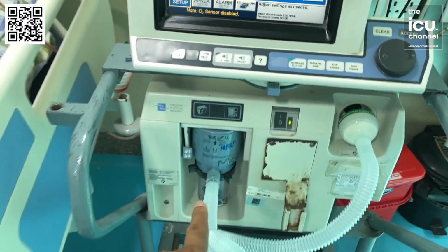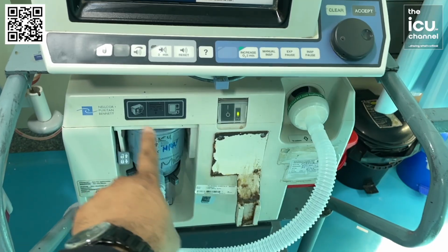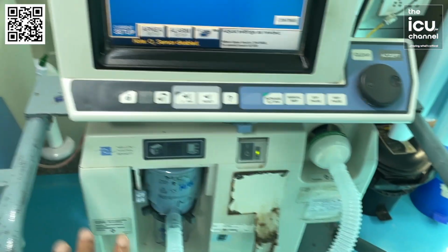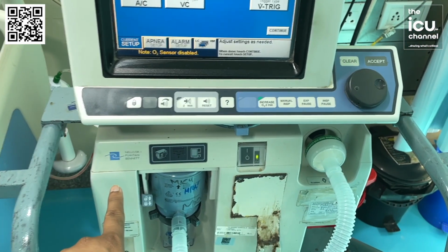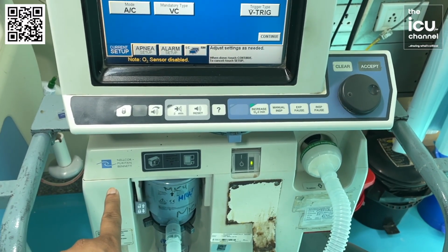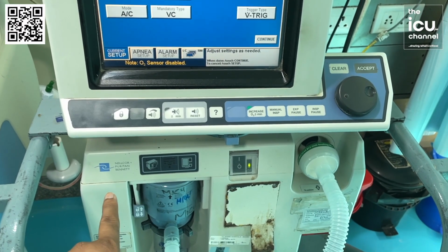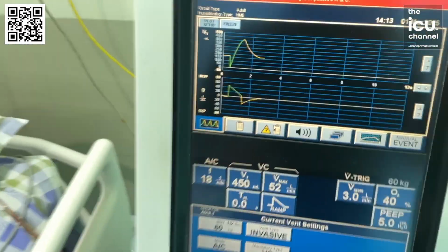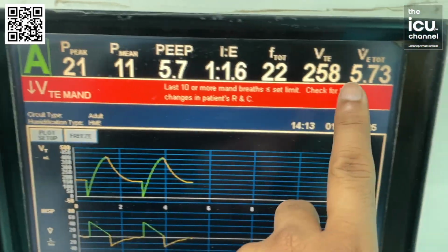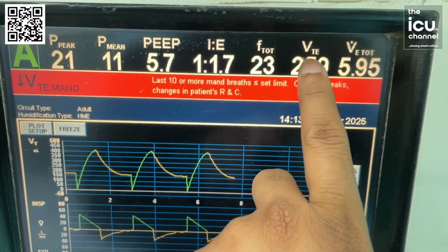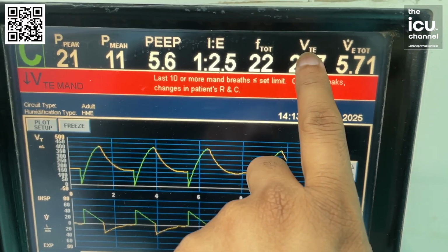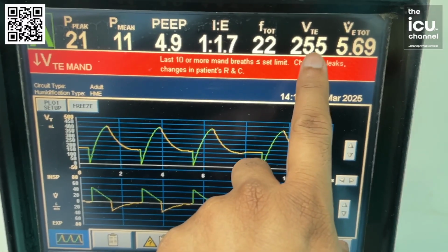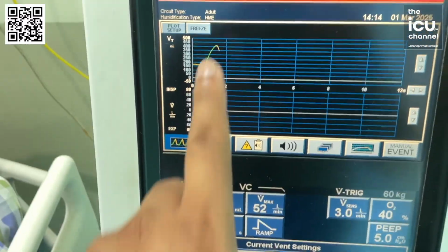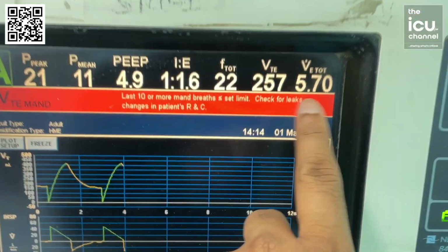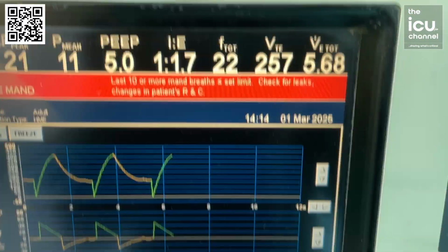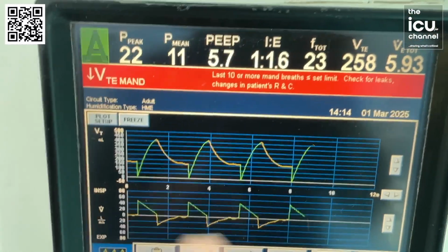Now, the expiratory tidal volume is getting returned via this filter, and it is being sensed by the flow sensor. How much amount is it receiving? We'll see where it is shown on the ventilator. So we are seeing this here. You see ventilator tidal volume. This is expiratory tidal volume, but here it is 257, 256. So 450 is getting to the patient, but in return, the expiratory limb is showing only 257. So that means there is something wrong.